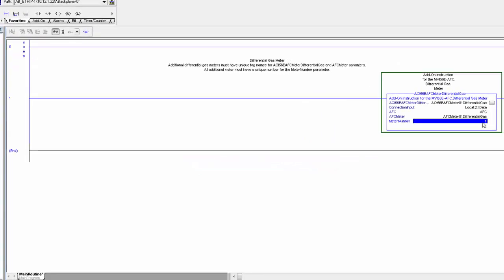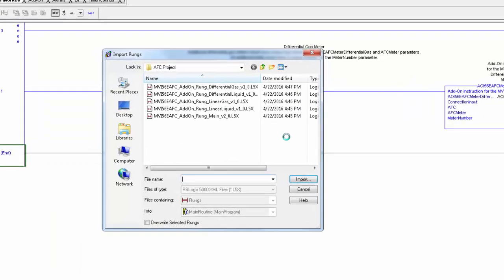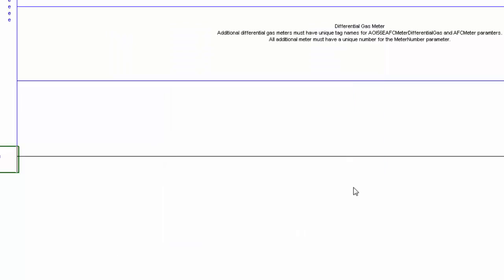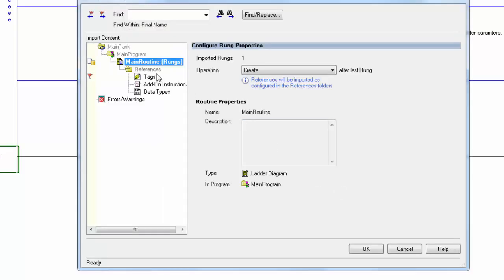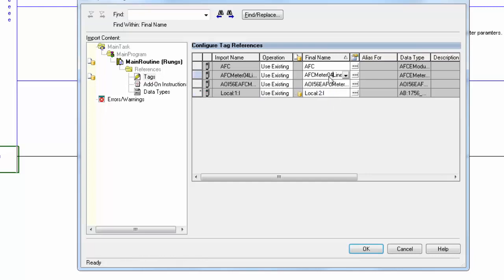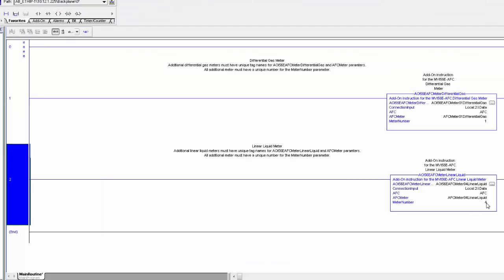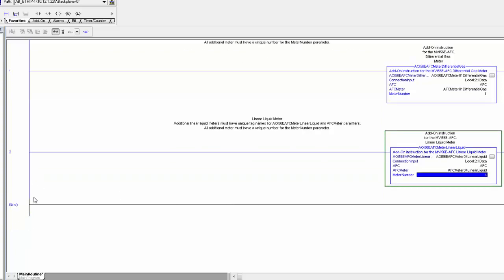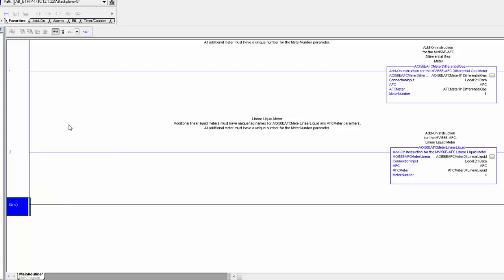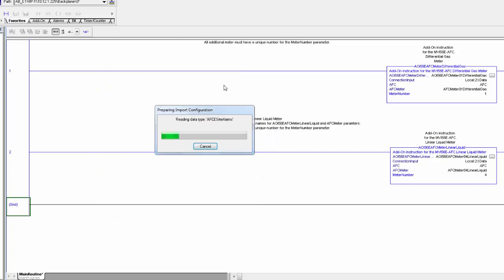I also want to be able to get data from a turbine meter measuring NGL, so I'll also bring in the Linear Liquid AOI. These meter-specific ladder files can all be placed in the same rung, and each AOI imports with a different meter number of 1 to 4. After the imports have finished, there is now a third location to update the meter number. Once you have imported the AOIs for all meters in your project, you will need to import the main MVI56E AFC AOI.